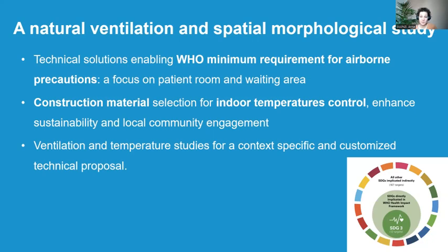The ventilation study developed for the treatment centers in Uganda aimed at considering as requirements the WHO minimum requirements for airborne precaution in terms of airflow rates and airflow direction within the facility. Regarding the selection of construction materials for the indoor temperature control strategy, particular attention was paid to sustainability and local community engagement. The outcomes of the study are context-specific, but the methods of work could be replicated for other contexts.